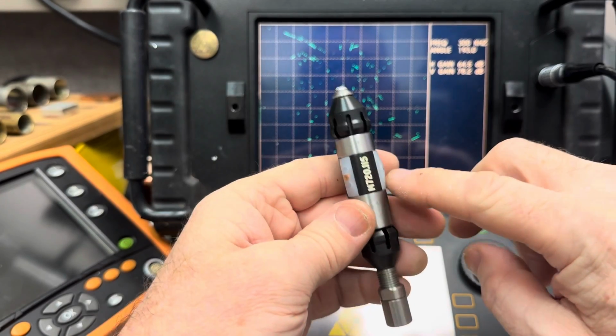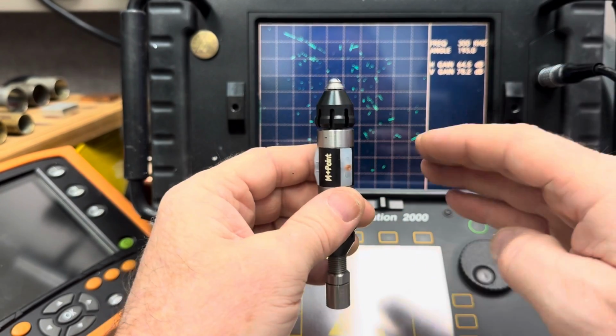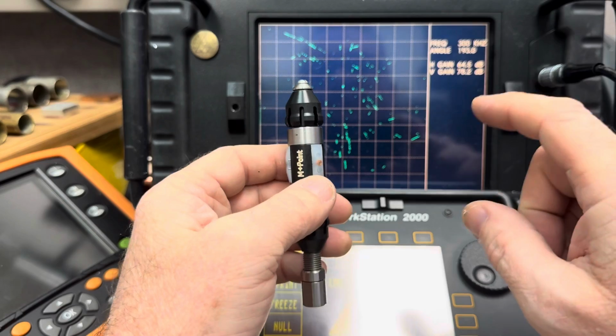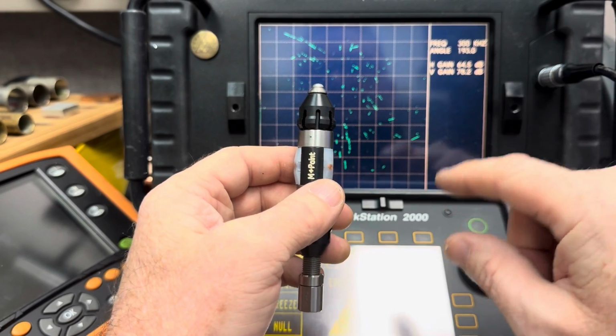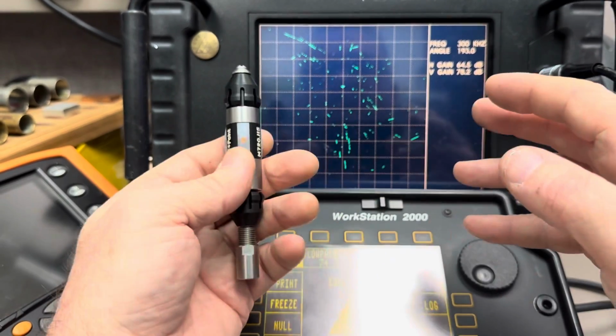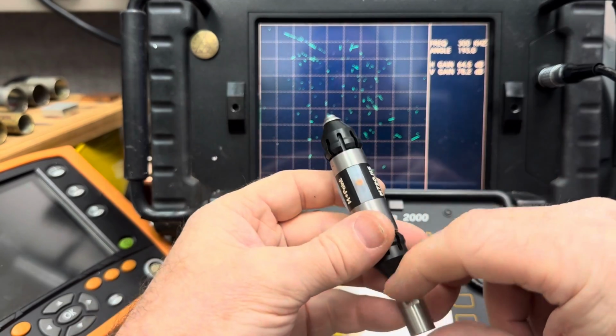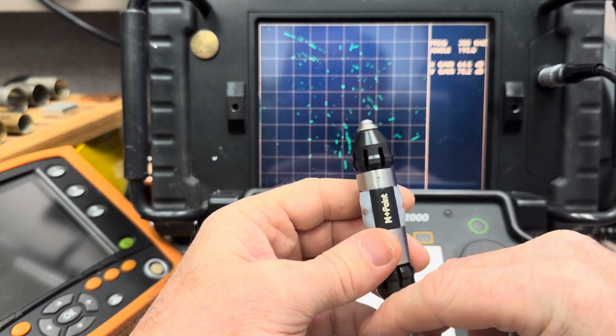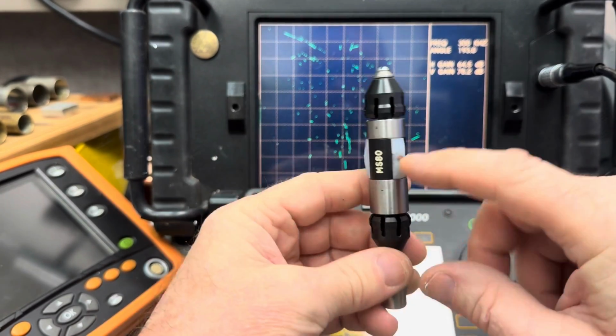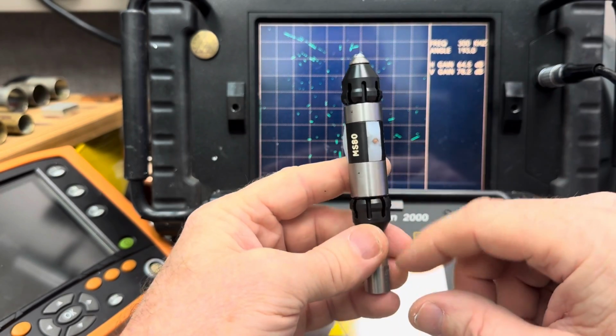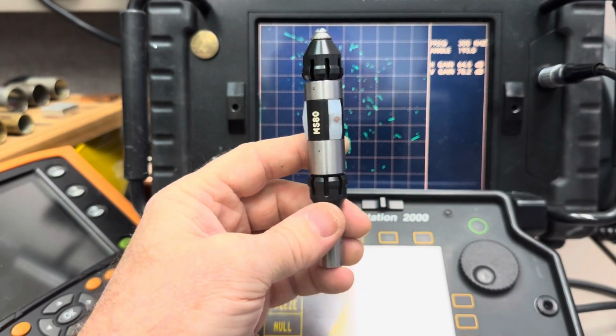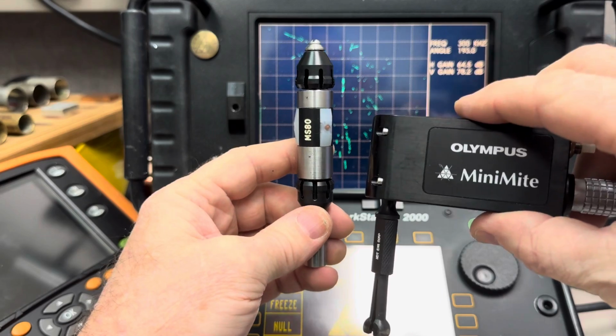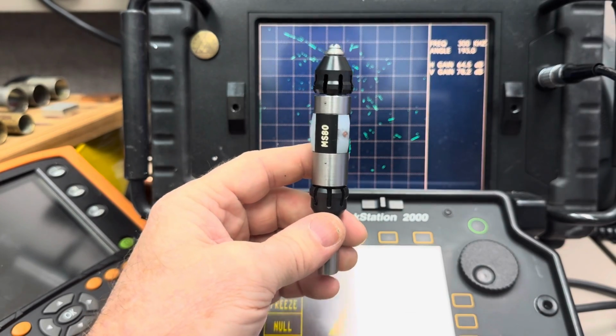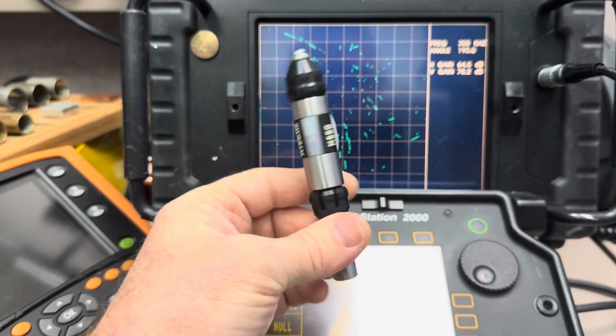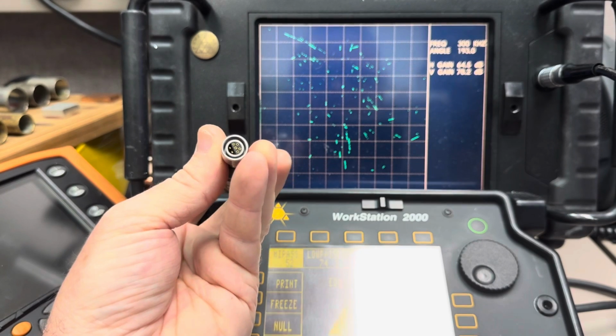And then the third coil, you would slew that 240 degrees. So now when you click through channels 1, 2, and 3 for the 3 different coils, they'll always be in the same spot in your terrain plot. So it makes data analysis much easier. Now, as you can see, this is a straight body probe. And this scanner is your motor unit. It spins the probe. Well, there's no motor in this probe head, but there is a connection point.